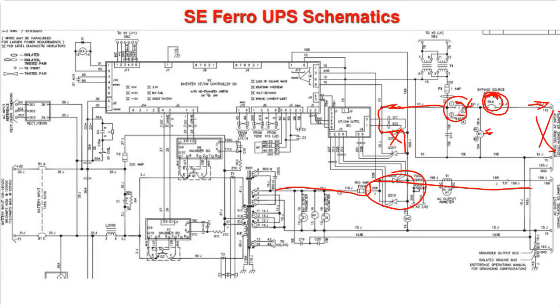And that means if somebody is working back on the MCC, we don't backfeed power onto that system if we have a failure in this static switch. So it's a UL safety mechanism to prevent that. It's kind of like if you had a generator on your house, you have to have the protection in place so you don't backfeed onto the pole and kill a lineman, basically, if he goes there to fix it.